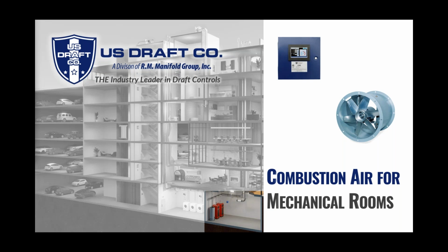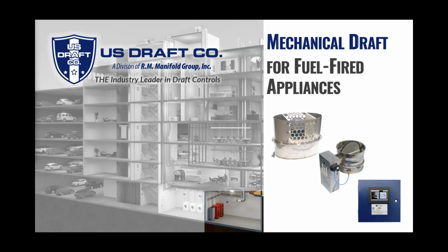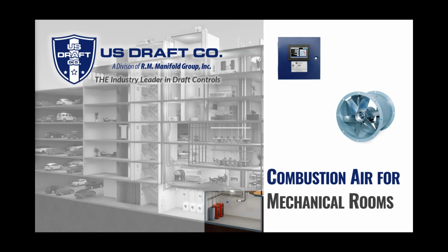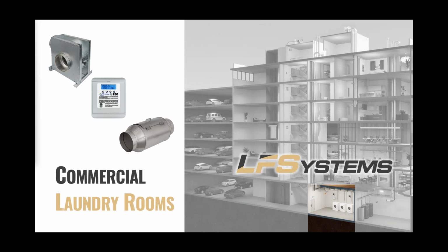Combustion air for mechanical rooms: instead of having big louvers in the dead of winter that are usually covered up by the operators because they don't know why they're there, we can do a smaller opening with a fan and dump fresh air into the space to make sure you have enough combustion air. Commercial laundry rooms: everything we do on the boiler side, we can also do for laundry spaces. So dormitories, hospitals, hotels, laundromats. We can common duct laundry exhaust as well as the makeup air, all with one single controller.